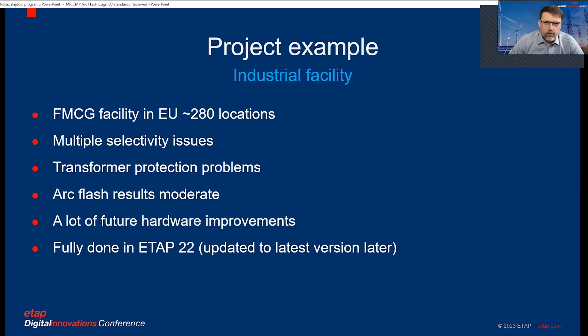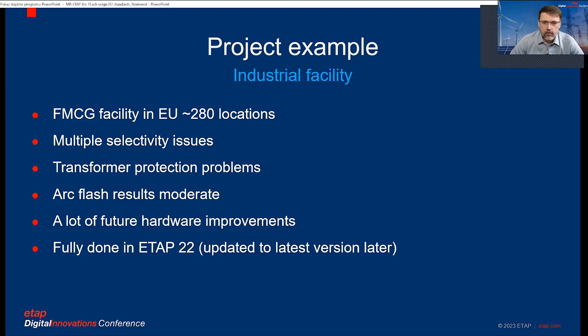So that was pre-version 22. Luckily we now have ETAP 22. I want to show you the project example I did for both IEEE and DGUV, modified slightly for this presentation. The project has 280 locations — it's a fast-moving consumer goods site. There were multiple selectivity issues, transformer protection issues. Initial results were actually low to medium — not very high — but you'll see the influence of that.